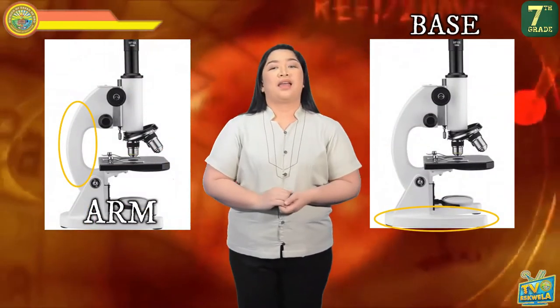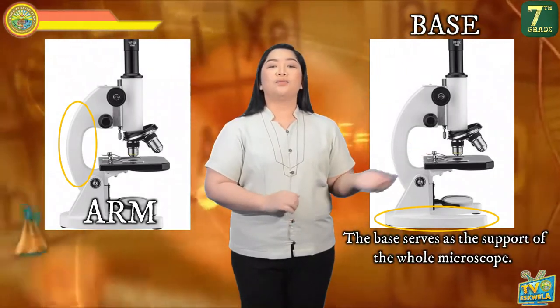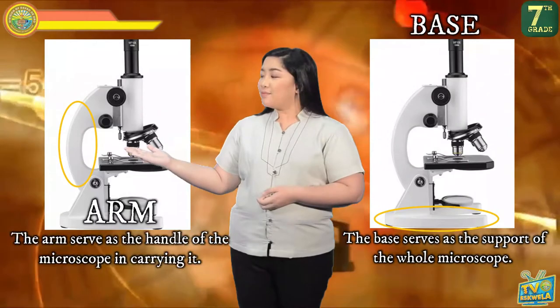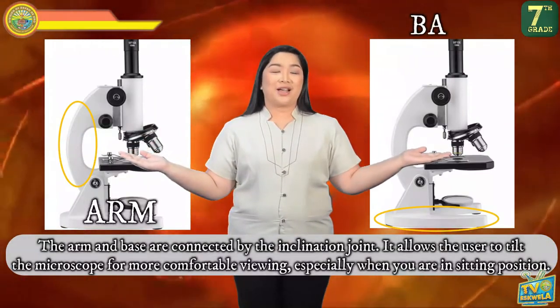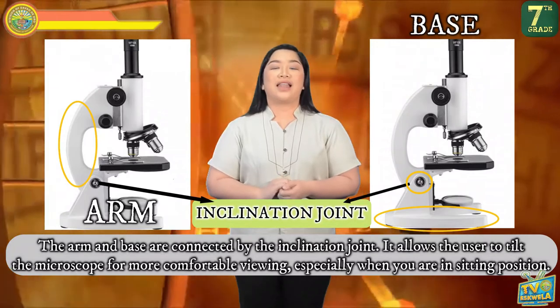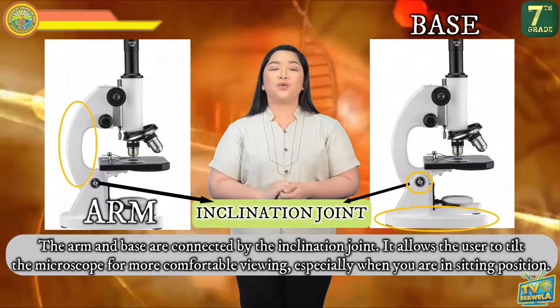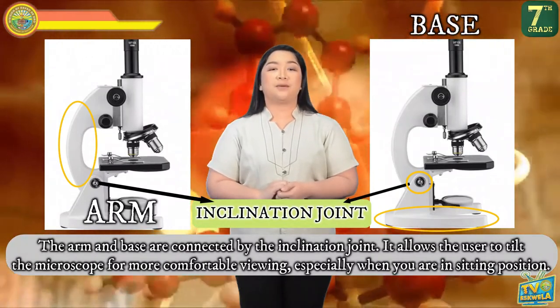The arm serves as the handle of the microscope for carrying it, and the base serves as the support of the whole microscope. The arm and base are connected by the inclination joint, which allows the user to tilt the microscope for more comfortable viewing, especially when sitting. However, you must only tilt the microscope when working with dry specimens. Tilting with liquid specimens can cause liquid to spill and flow into the metal parts, causing rusting which can damage the microscope.